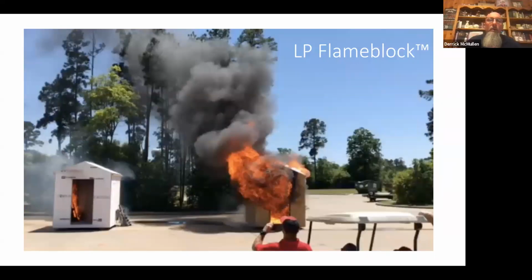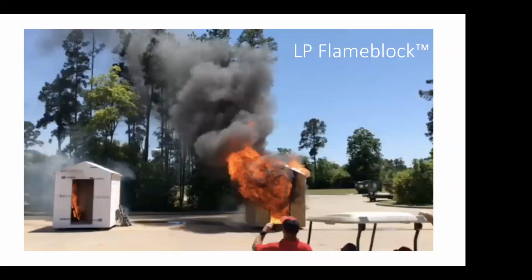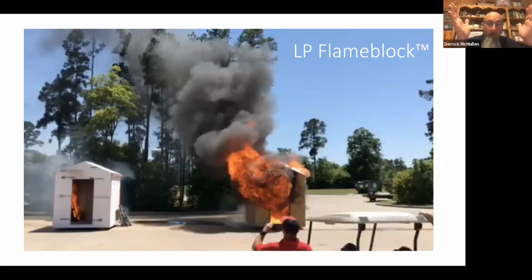It will be, well, there's different ones. Typically, if you have 5/8 Type X on each side, you're going to have an hour. But the plan should say what is going to be required on there. And the only time that you're going to be calling it out, typically, if it's not meeting the requirements, is at probably a pre-drywall inspection, or if the client specifically calls you out for that, because at final construction, you're not going to be able to see what's there unless there's holes in it and it's compromised. And that brings up a good point too. Older townhomes, he almost said condos.